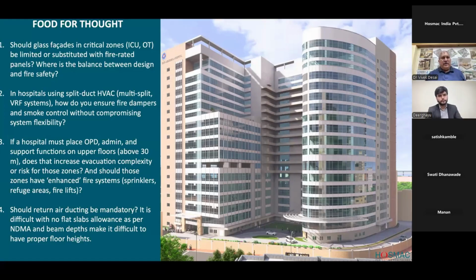Then the last point, Satish, again for you: should return air ducting be mandatory? This is something we are having some problem with in some cases where CFOs say that return air ducting should be mandatory. And it becomes difficult because of the height restriction of the building. We are not allowed to have flat slabs. So we have a beam, below which the duct goes. So what is your take on this? Should it be mandatory or discretionary?